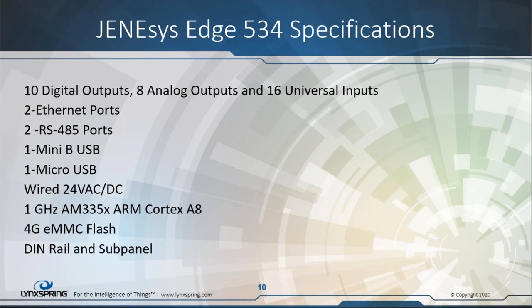It has 10 digital outputs, these are relay outputs rated for 0.5 amps. There are 8 analog outputs, those range from 0 to 10 volt DC signals, and 16 universal inputs, which exemplify the same things you would see on an IO34 device using a regular Jace. That was our goal, to keep the characteristics of our IO the same as someone who's used to an IO34 or IO16, so they could apply it quickly to an Edge device.